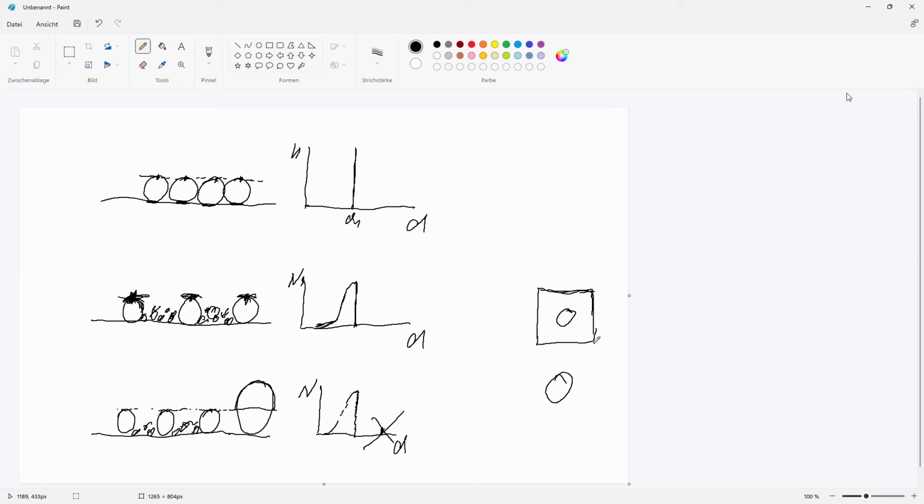There also exist other principles, the Coulter principle, where you can really measure the volume of the particle. Here you can measure only in 2D, but the Coulter principle can measure the particles in 3D, and these devices measure, for example, 10,000 particles in a minute, 2 minutes, so in this time range.